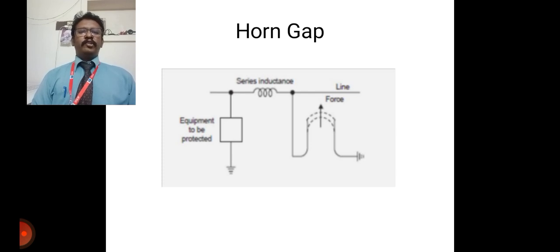There are two major drawbacks in the horn gap. One is that the time of operation of a gap is quite large compared to modern protective gears. And the next one is that if used on an isolated neutral, the horn gap may constitute a vicious kind of arcing grounds. For these reasons, the horn gap has almost vanished from important power lines. So nowadays, it is an outdated one. These are the points you have to keep in mind while writing about the horn gap.